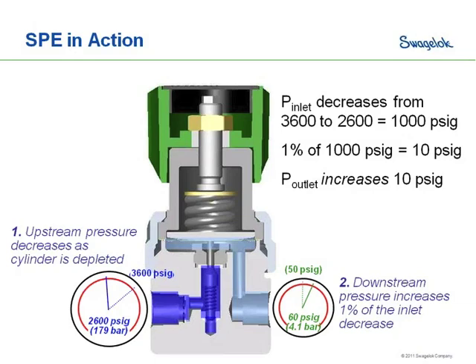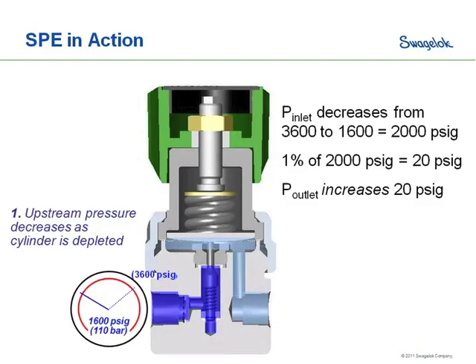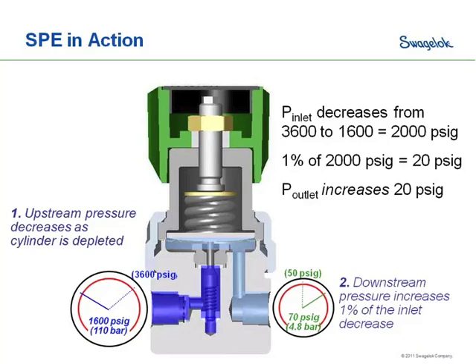And this is all just because of that balancing of forces internal in our regulators. Continuing the example, if we dropped another 1,000 psi, because we continue to deplete our pressure in our cylinders, now we're down from 3,600 to 1,600. 1% of that decrease is 20 psi, so our outlet pressure is going to rise from 50 psi up to 70 psi.